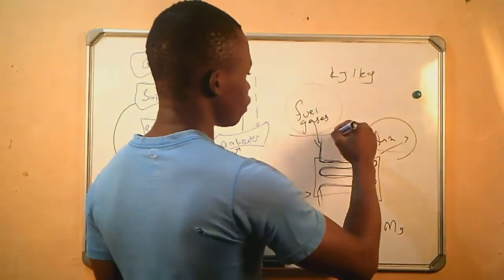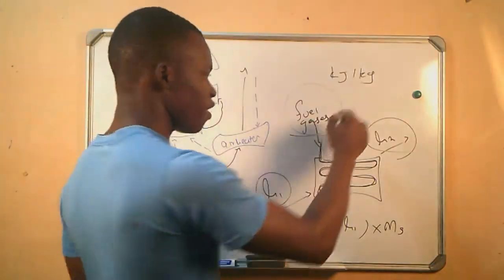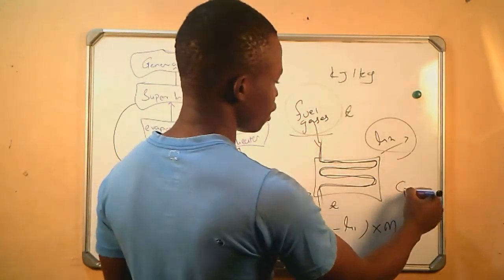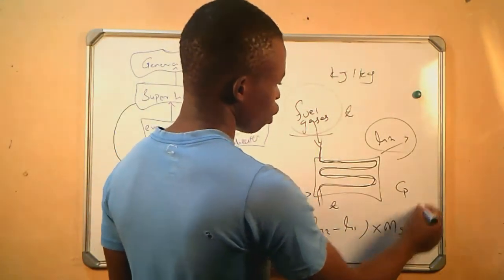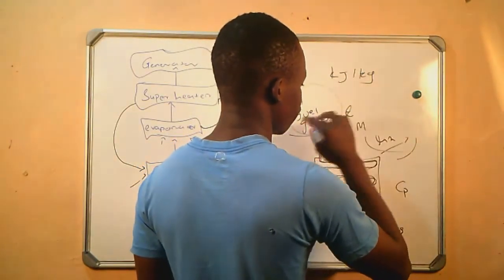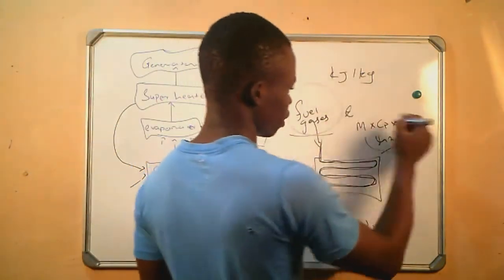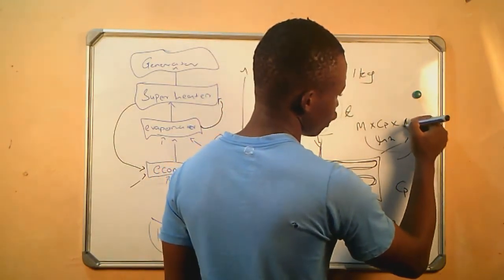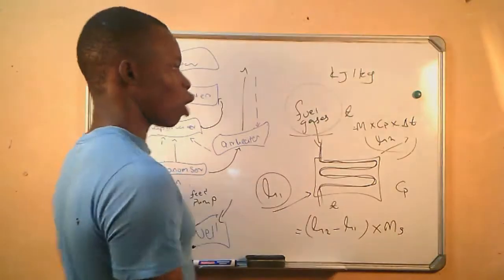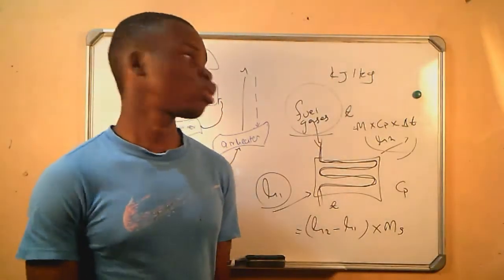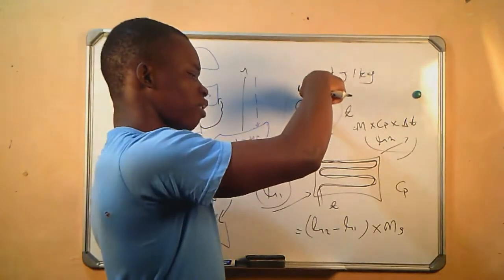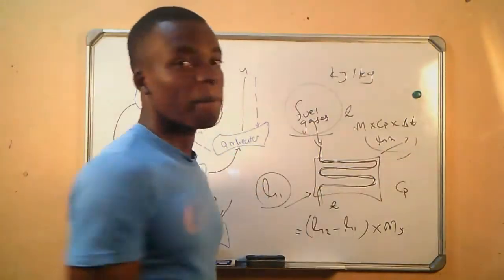To get that, you can also use the information of the fuel gases if you are given it. If you are given the temperature before and the temperature after, and you are given the specific heat capacity of the fuel gases, you are going to use the formula: mass of the fuel gases times the specific heat capacity at constant pressure — since everything takes place at constant pressure here — times the change in temperature. This gives us the heat that was lost by the fuel gases. According to the law of conservation of energy, the heat lost by the fuel gases is equal to the heat gained by the feed water.